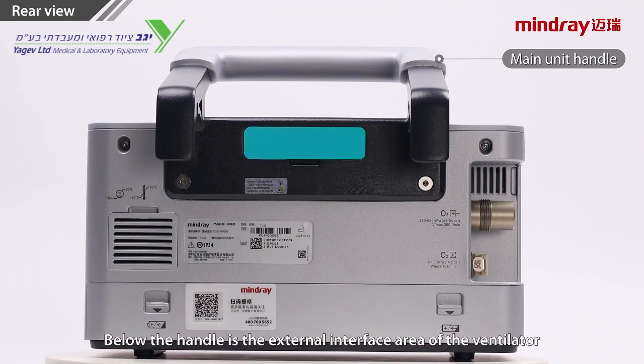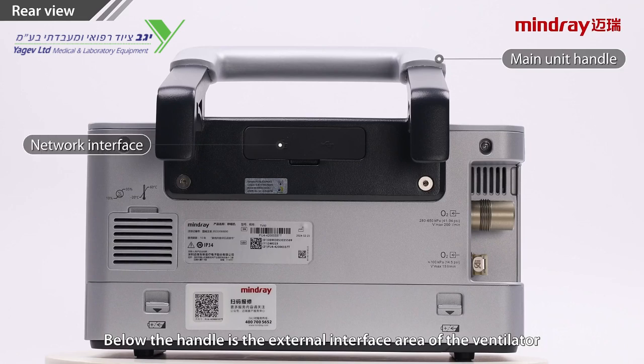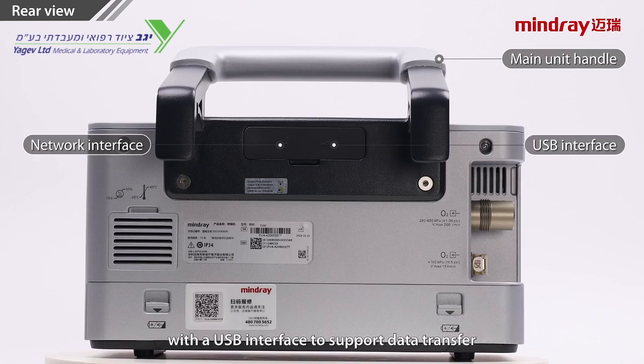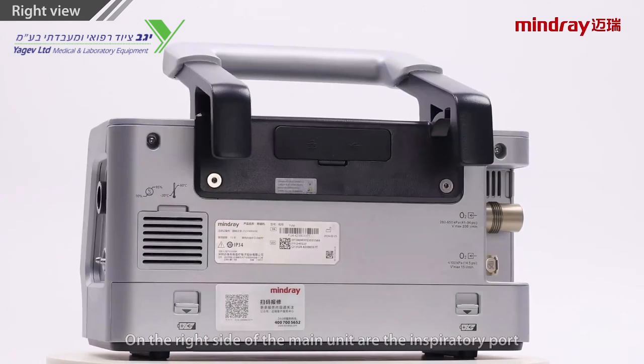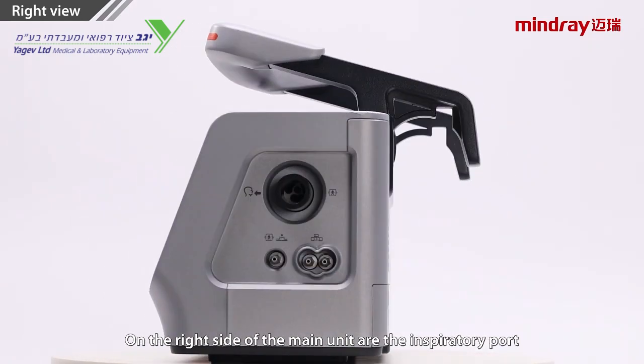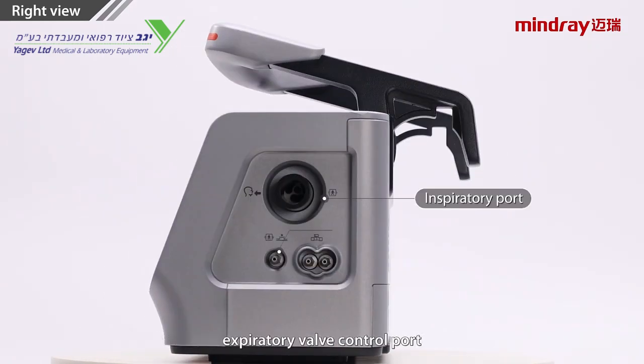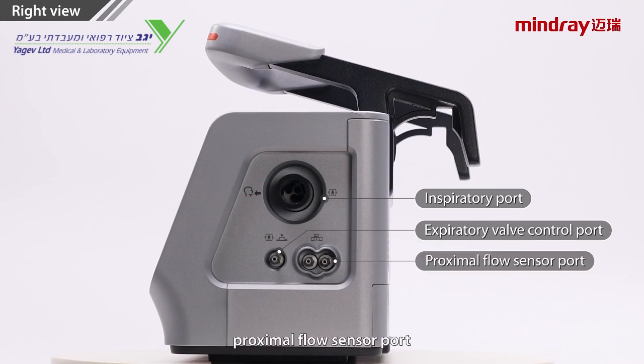Below the handle is the external interface area of the ventilator with a USB interface to support data transfer and a network interface to connect to the hospital network. On the right side of the main unit are the inspiratory port, expiratory valve control port, and proximal flow sensor port.